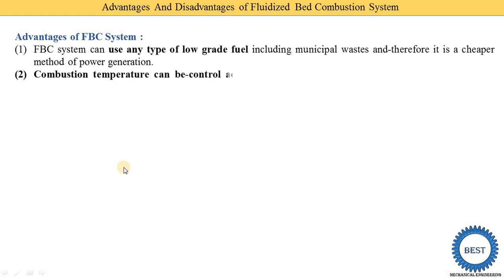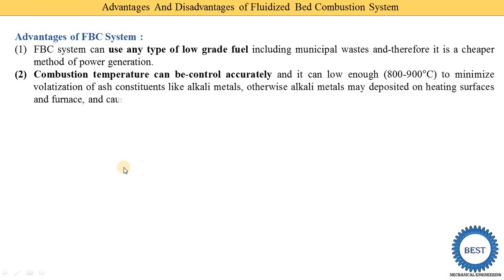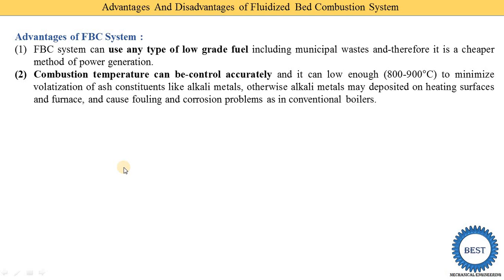The second advantage is that combustion temperature can be controlled accurately and kept low enough at 800 to 900°C. At this temperature we are able to minimize volatilization of constituents like alkali metals. Otherwise these alkali metals may deposit on the heating surfaces and the furnace.